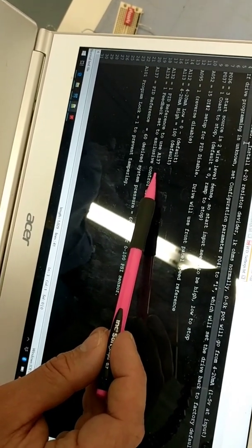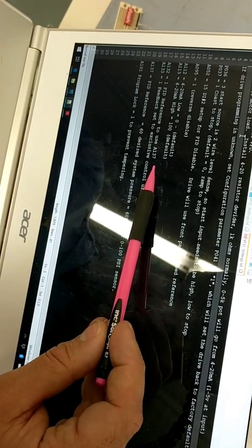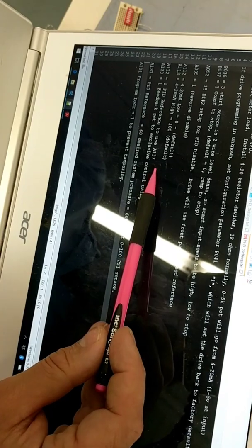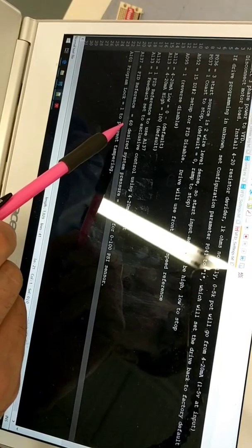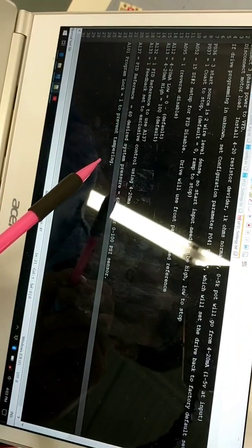A132 PID reference, set that to 1, and then that's going to use the parameter in A137 as the PID reference. So for a sensor from 0 to 100 PSI, this value can go anywhere from 0 to 100%. Conveniently, we set that to 60 for 60 PSI.